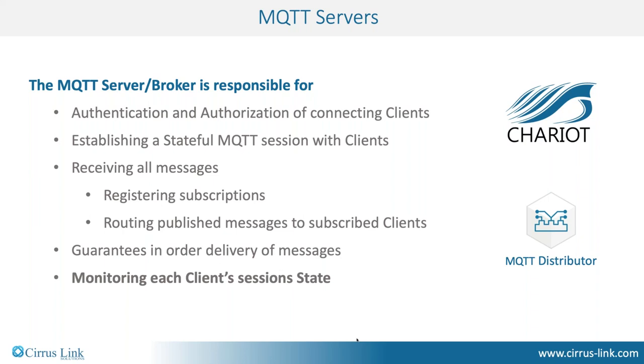An MQTT 3.1.1 server must guarantee in-order delivery of messages. For example, if a valve state goes from open to closed, those two messages must be delivered in order so they don't get out of sync. The MQTT server also monitors all connected clients, and if any fall off the TCP/IP network it is responsible for publishing that client's last will and testament — what we call the death certificate. For instance, if a node monitoring an oil well loses cellular connectivity, you need to know in real time when that event happened.